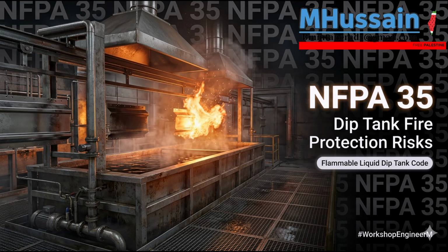Okay. If your plant is out in a remote rural county with a volunteer department that takes 30 minutes to arrive, or if the local water infrastructure just can't support heavy flow rates, you do not have protection for exposures. So the standard steps in. Right. Yeah. The standard compensates for this lack of human intervention by forcing you to buy more land. It uses physical distance as the ultimate fail-safe buffer. It's brilliant because it mathematically links local municipal infrastructure directly to the facility's real estate footprint.